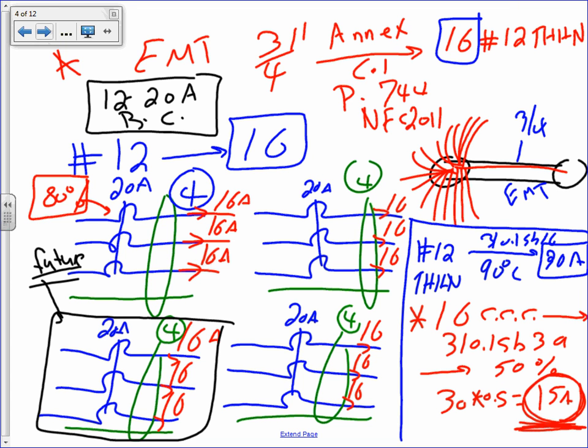Okay, so 50 percent, 50 percent of 30 will give you 15 amps. How many amps have I lost by grouping them? This is how many amps you lose when you group them, and this is how many amps maximum they can carry anyway. How many amps did they lose by grouping them? 1 amp. Do you see why grouping them is not a big deal in terms of the rating? I use this one, guys, so I lost only 1 amp by grouping all these 12 circuits, 12 20 amp circuits.